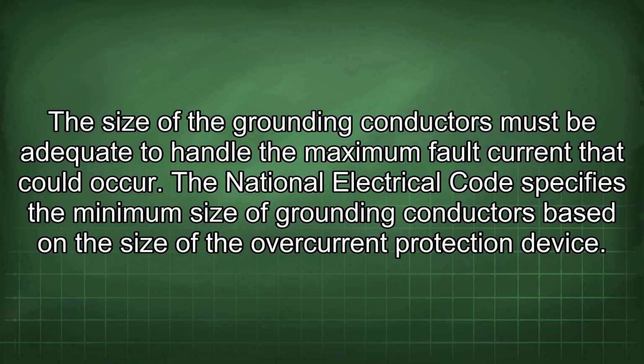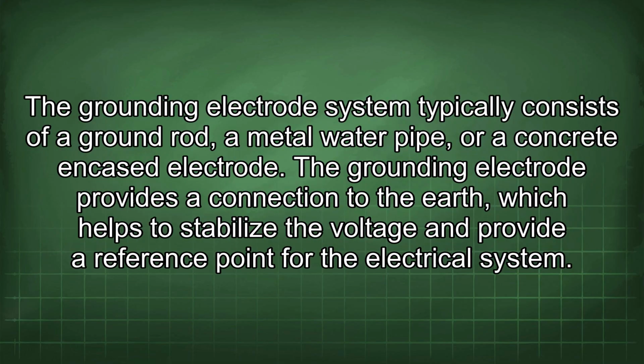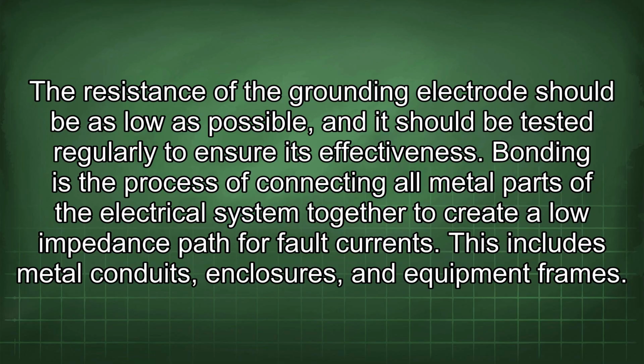The National Electrical Code specifies the minimum size of grounding conductors based on the size of the overcurrent protection device. The grounding electrode system typically consists of a ground rod, a metal water pipe, or a concrete encased electrode. The grounding electrode provides a connection to the earth, which helps to stabilize the voltage and provide a reference point for the electrical system. The resistance of the grounding electrode should be as low as possible, and it should be tested regularly to ensure its effectiveness.